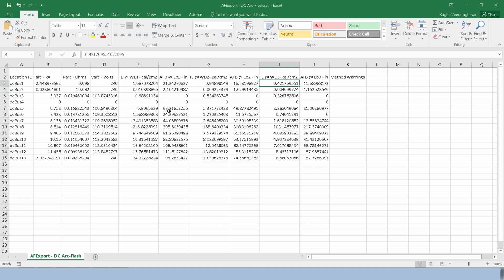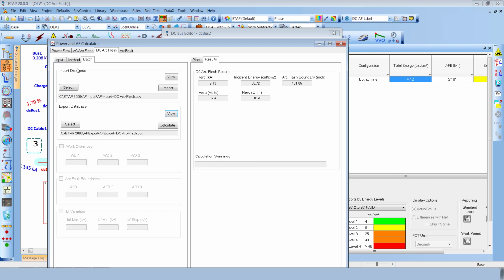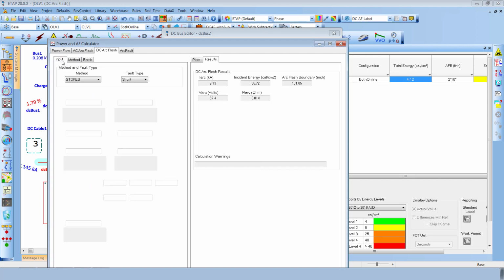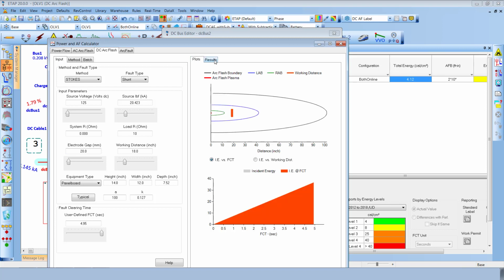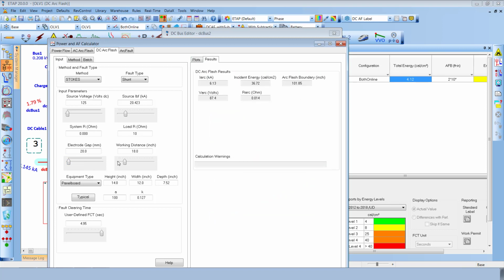This tool will be very useful to do a preliminary arc flash study before even setting up all the scenarios in ETAP 20, and it is also very powerful to determine the combination of several methods that could be used from the standalone calculator that is available in ETAP. ETAP also has the flexibility to account for a quick calculator that could easily provide an incident energy evaluation depending upon varying any of the system parameters or the corresponding fault clearing time respectively.